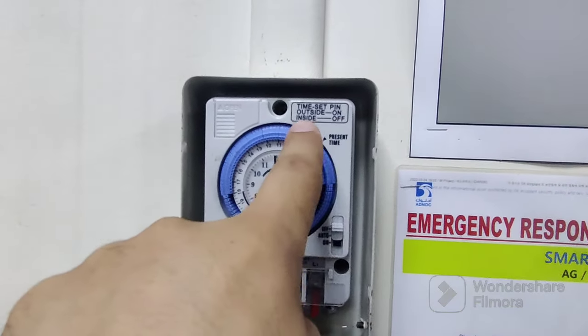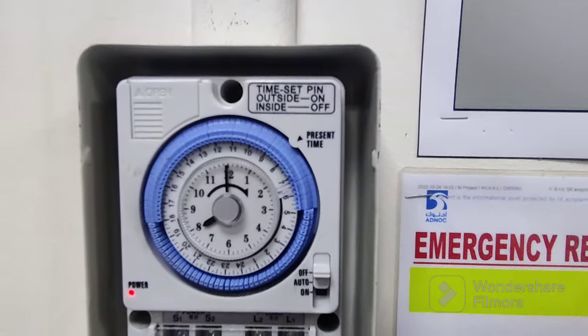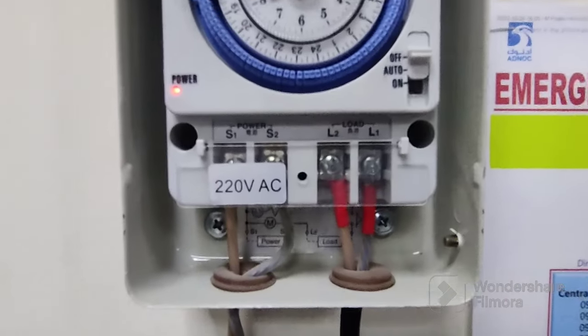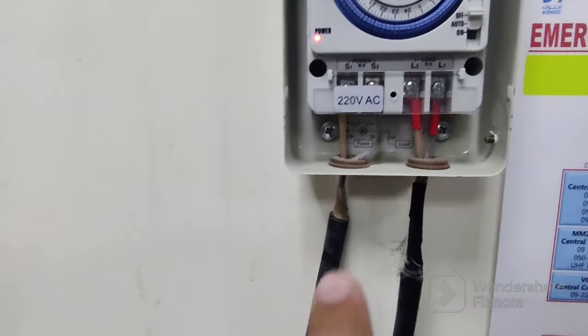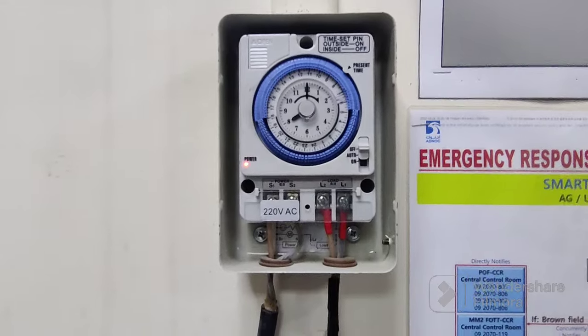I will show you how to fix the timing — which time you want to switch on and which time you want to switch off. Look at the overall view: the light is on, which means the timer switch is on and there is a power supply. It's a 2.5mm square cable. We mounted this unit to the wall using two screws, one on each side. Now I will tell you how to set the timing.